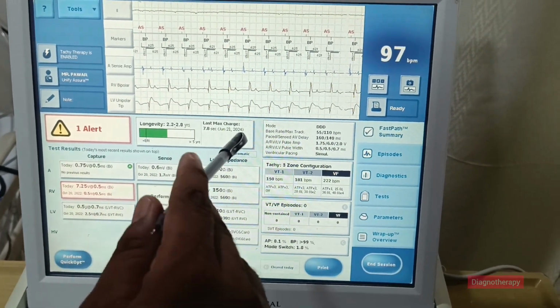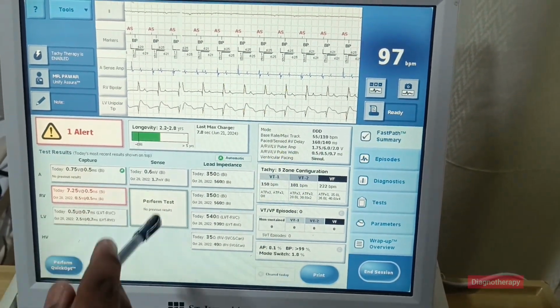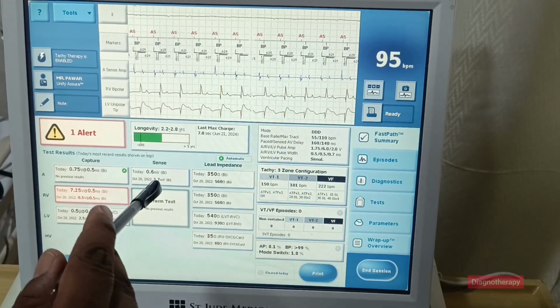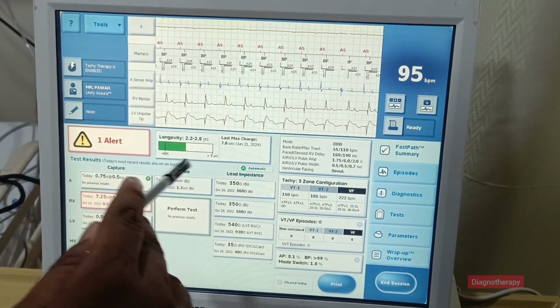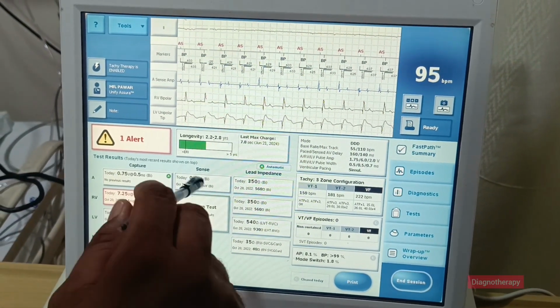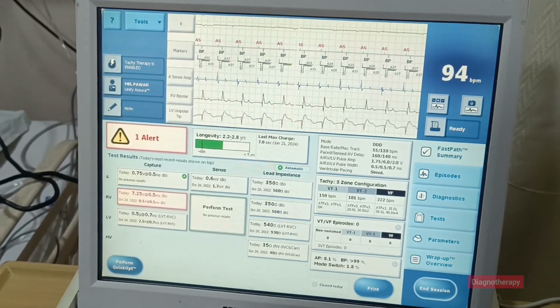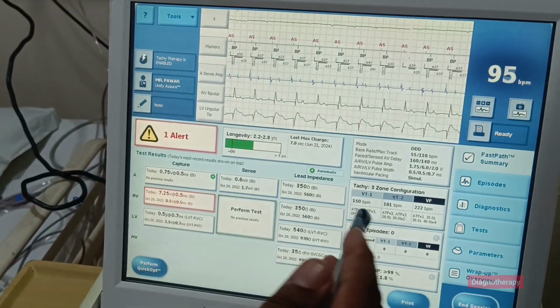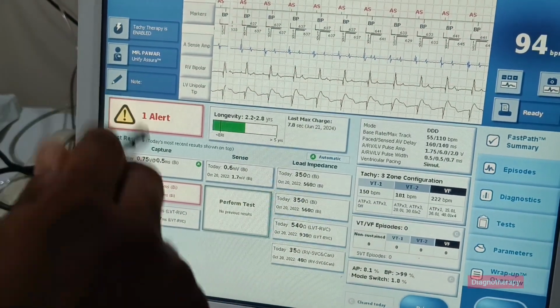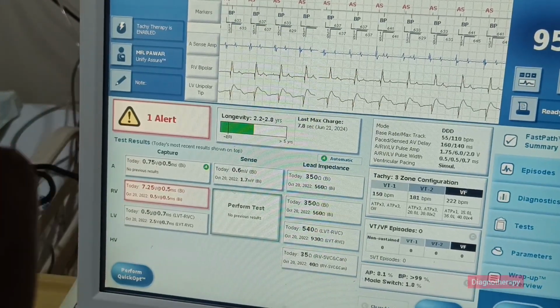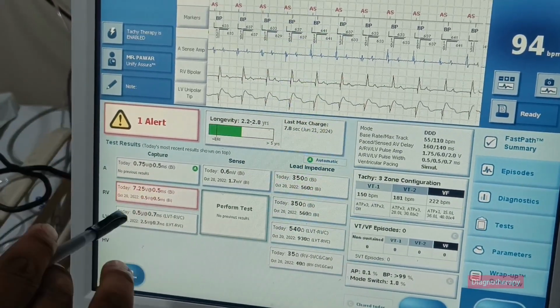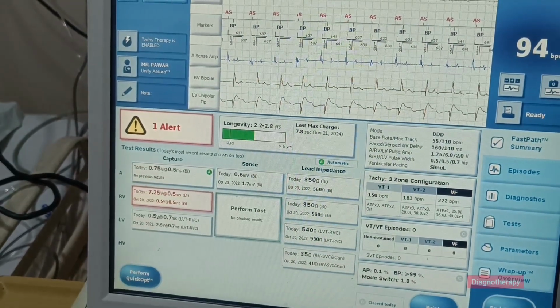Here the sensing is very important. With the right type of sensing of voltages and right sensing of the heart activity, the further voltages are calculated and given to the respective chambers. With calculation of impedance, the voltages are set. The more voltages are set, the lesser the battery life will be, and the lower the voltages are, the more the battery life will be.